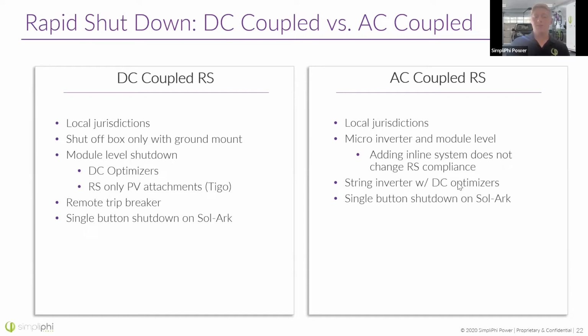Sometimes you'd need a way to remotely shut down the whole system with one button. So this is something we're seeing increasingly in AC and DC coupled systems alike across multiple jurisdictions, but I'd say the more strict ones are actually requiring a single button that you can press that's accessible to firefighters, near the system, in the garage or outside, that is going to disconnect the batteries, disconnect the PV array, and turn off the inverter all in the press of one button. Now, this specifically is a big selling point for the Sol-Ark inverter because it has all these features built into it. It's got this ability to have a single button be pressed and cause all this to happen.